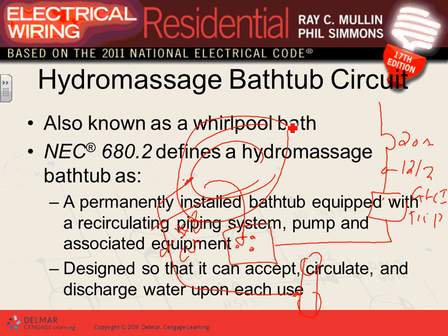Now, Adam, where's the disconnect for this hydromassage bathtub? The plug. Where's the overload? Built into it. Where's the overcurrent protection device? Right here. Where's the branch circuit? Here. GFCI is just because it's dealing with water, we need to make sure it trips if there's any leakage to ground. The overload is built into the hydromassage?